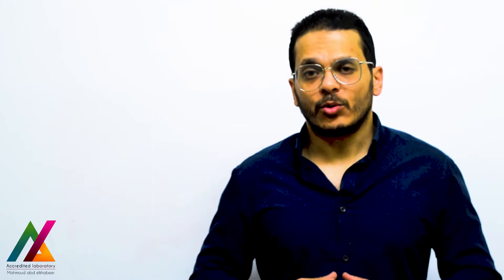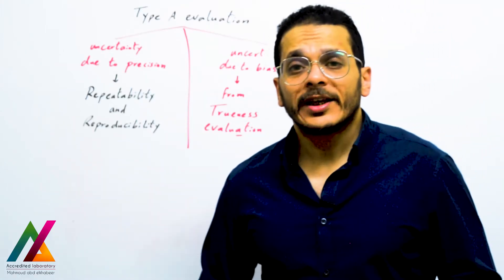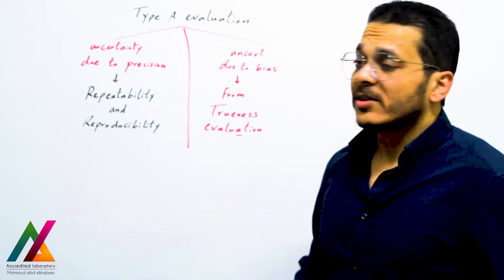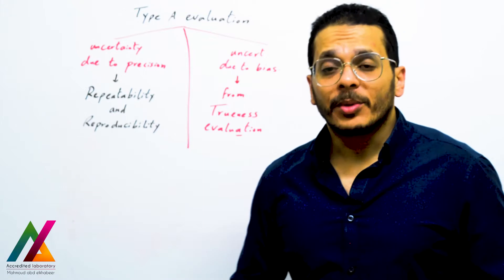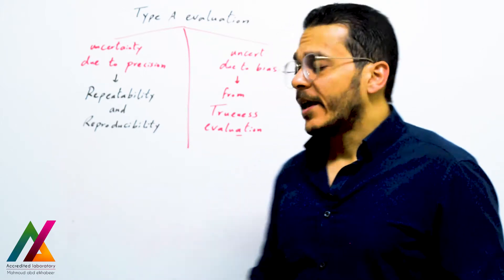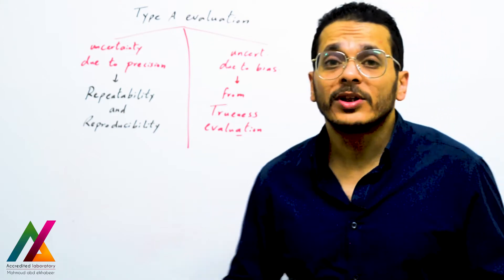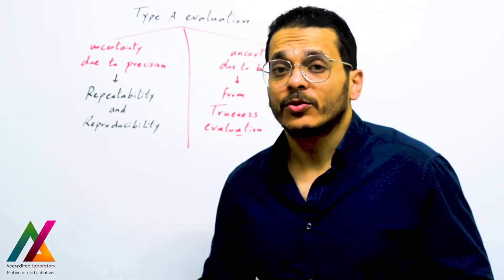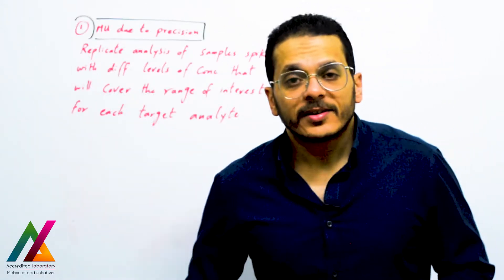According to the Eurachem guideline, you have two ways: Type A evaluation and Type B evaluation. From Type A evaluation you will get two values: measurement uncertainty due to precision, which comes from repeatability and reproducibility, and measurement uncertainty due to bias, which comes from trueness evaluation. Bias is the measure of trueness.